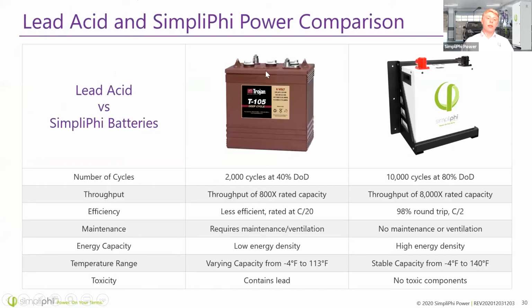So, a comparison between lead acid and Phi. Again, I'm just using Trojan because they have the most available data. A Trojan battery is rated to 2,000 cycles at 40% DOD. That chart is actually on the first slide as well, where you can see the number of cycles it's rated to at different depths of discharge. This means it's rated to a throughput of 800 times its rated capacity, just by multiplying 2,000 cycles times 40% depth of discharge. Now, a Phi battery is rated to 10,000 cycles at 80% depth of discharge. Multiplying those, you get 8,000 times rated capacity. So ultimately, 10 times longer lifespan in terms of throughput.